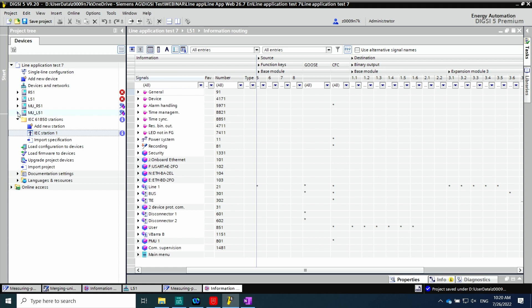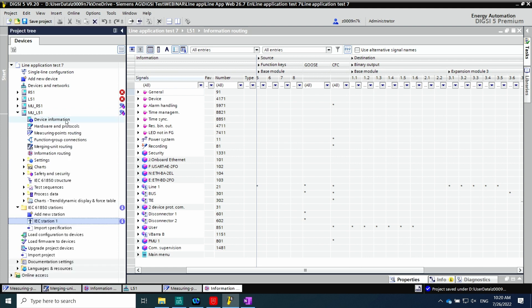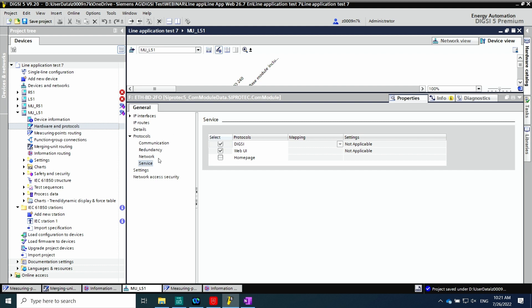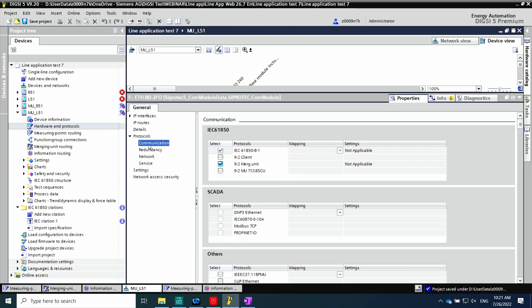Please refer to the first process bus video on transformer protection application with process bus, which explains some details that will not be repeated here. In hardware and protocols, we have the view of the merging unit. Here we have the expansion module IO 240 in position 3. This module permits us to bring the information from the low power instrument transformer into the merging unit. I will quickly show you the configuration of the Ethernet port — for more details refer to the first webinar. In protocols and communication, we need to select the IEC 61850-9-2 merging unit functionality.